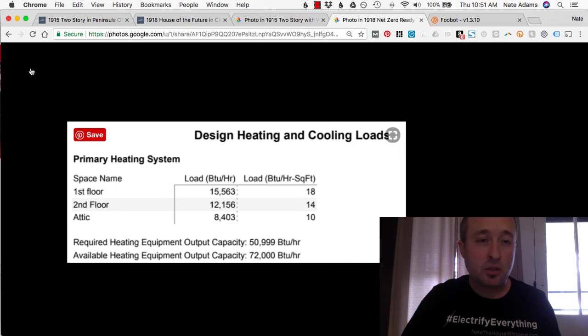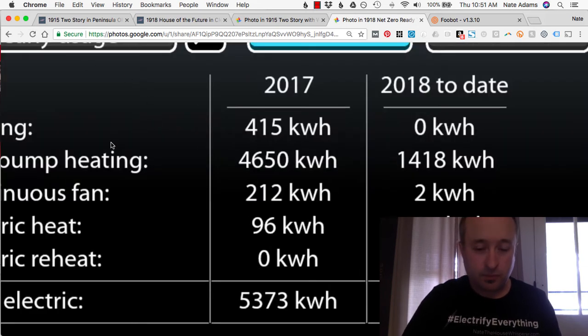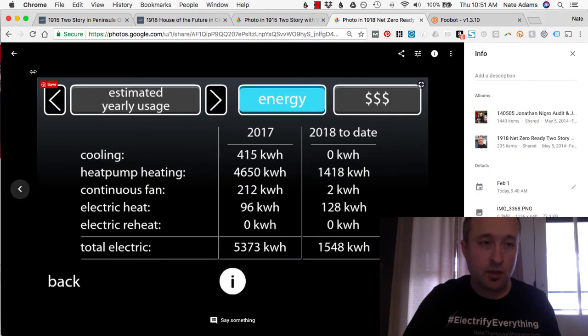Now John's house is a little bit more complicated. The key number to look at here is adding these two, the 15,000 and the 12,000, so it's about 27,000 BTUs to heat the first and second floor when it's 5 degrees out. Let's get that zoomed out.